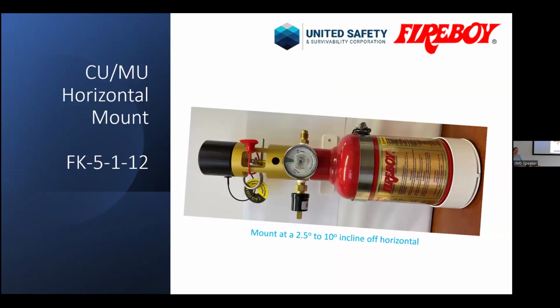With the change from HFC to FK, all our bigger cylinders have to be fitted vertically. They cannot be fitted horizontally, which has become a problem in some of the smaller engine spaces. So we have had to go through the fire testing and develop a new valve, which has only got one opening for the chemical to come through to allow for the horizontal mounting for the smaller spaces. These ones can only be mounted horizontally, so you cannot exchange vertical or horizontal. So part of the survey would be to make sure that the installation there is correct.